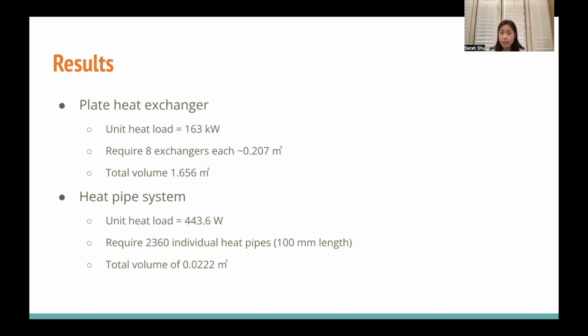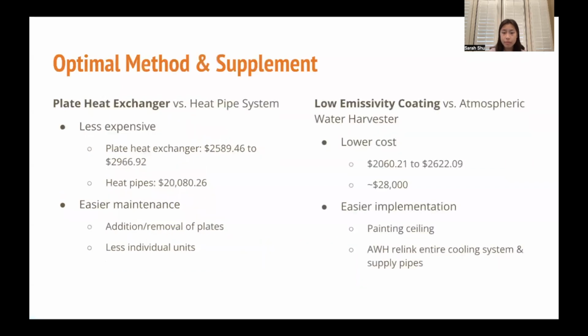As for the heat pipe system, its unit heat load was 443.6 watts and required 2,360 individual heat pipes of 100 millimeters each. Its total volume was 0.022 meters cubed. The choice between the waste heat recovery methods was the plate heat exchanger. Its upfront cost was a little more than 10% of the cost for the heat pipes.